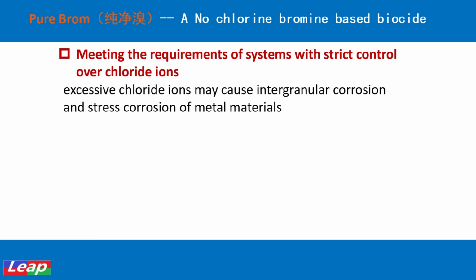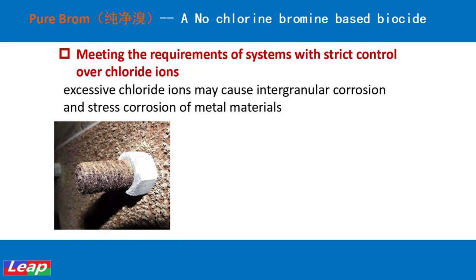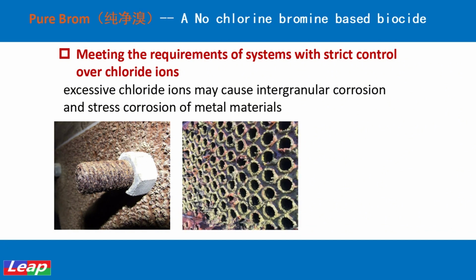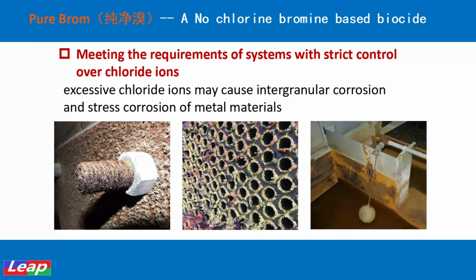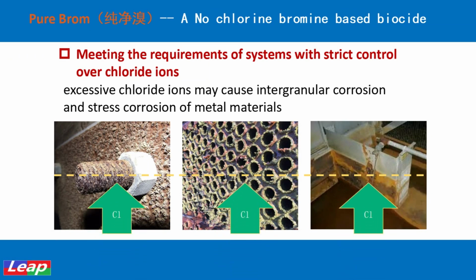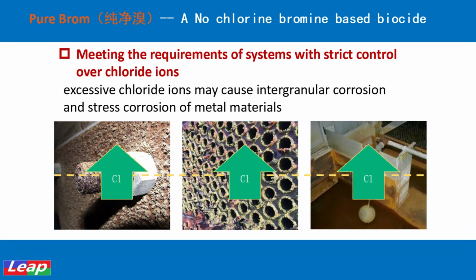In many water systems, such as cooling towers equipped with stainless steel heat exchangers, condensers, or structural facilities, excessive chloride ions may cause intergranular corrosion and stress corrosion of metal materials, resulting in equipment damage and unplanned shutdowns, increasing operational and maintenance costs, and posing safety hazards. For such systems, strict chloride ion control is crucial to prevent this. At this point, chlorine-based oxidizing biocides need to meet microbial control index requirements, while avoiding excessive accumulation of chloride ions, which is nearly impossible.